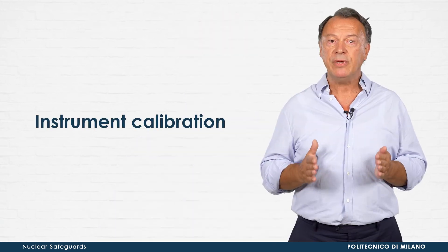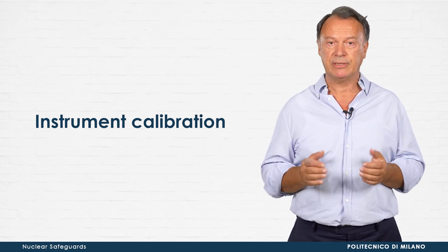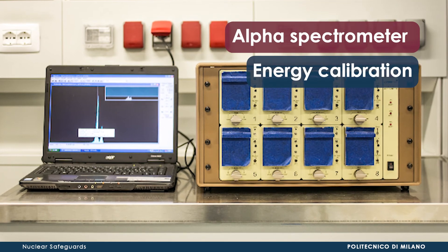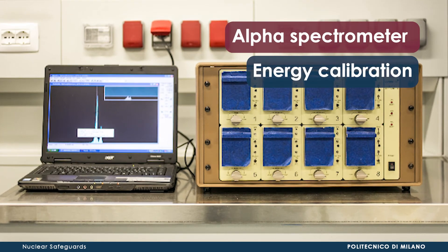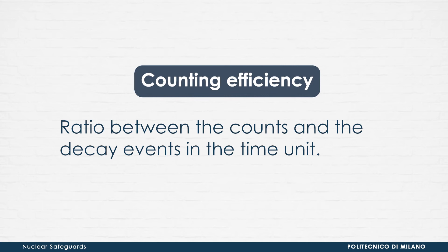Whatever radiometric technique is selected, in order to quantitatively assess the radionuclide concentration in the sample, the instrument has to be calibrated using suitable certified radioactive standard sources. For example, the alpha spectrometer needs energy calibration by means of a certified source containing several alpha emitters. Standard alpha sources with known activities are used to evaluate the counting efficiency at different energies, defined as the ratio between the counts and decay events per unit time.